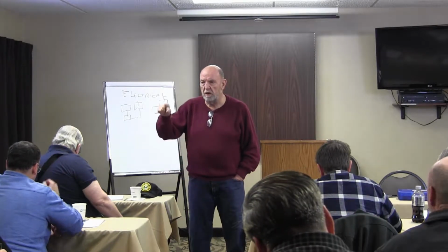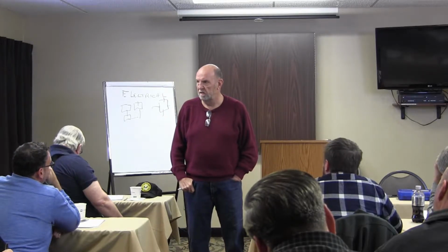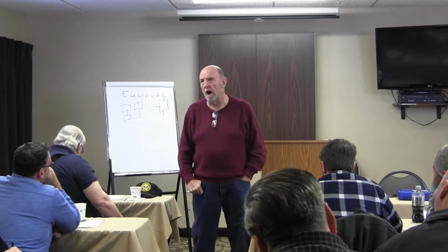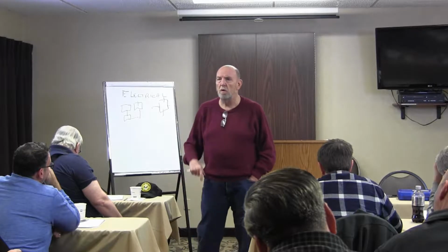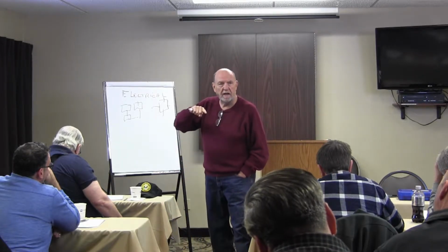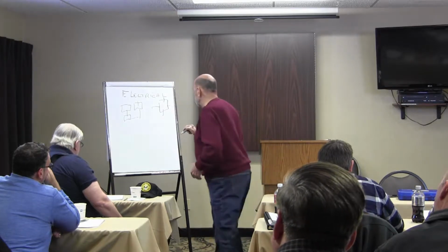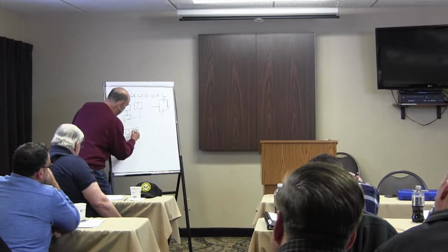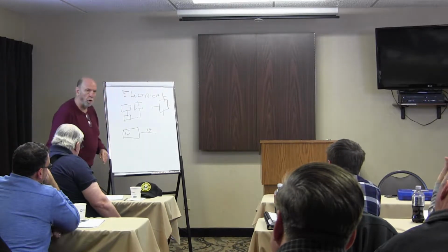Now, it's convenient that we do get to go in and turn on and turn off circuits, but the important thing is, as we're running wires throughout the house, that they come to some location where the rating can be monitored and adjusted, so that the breaker that is a 15 amp breaker would have a 14 gauge wire on it.